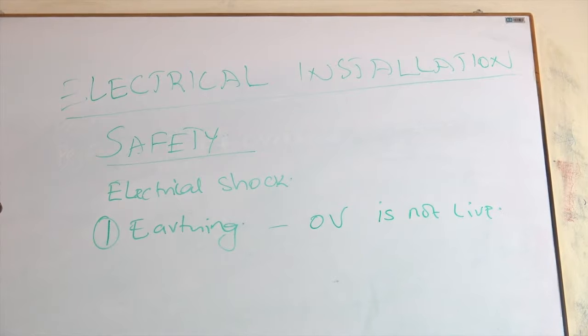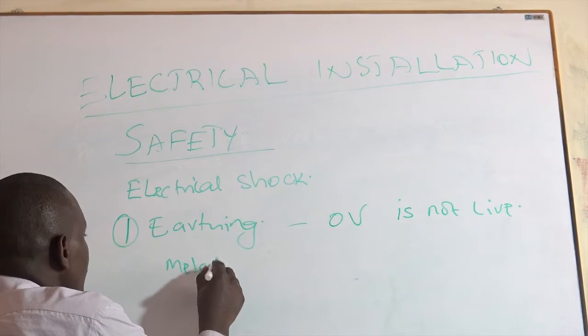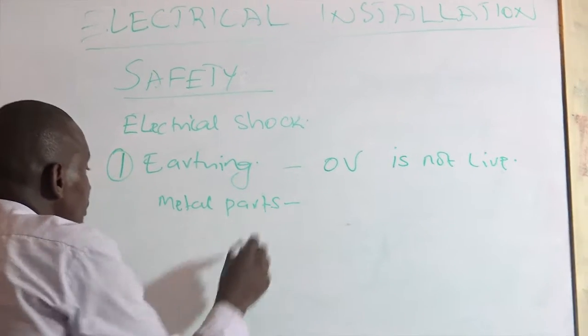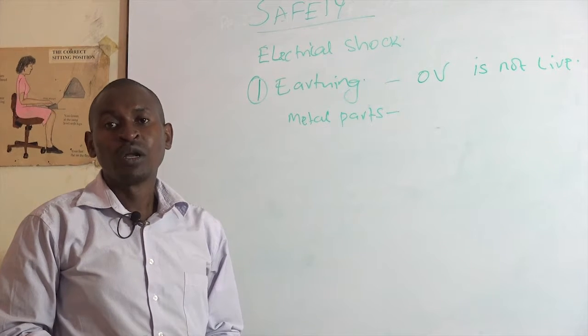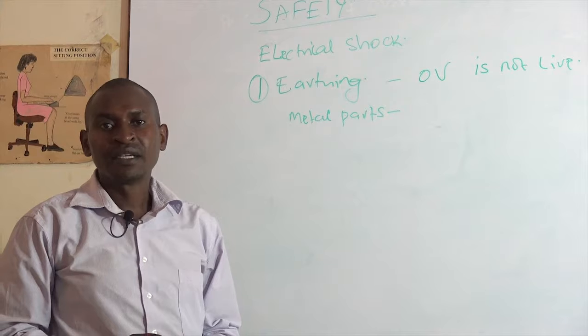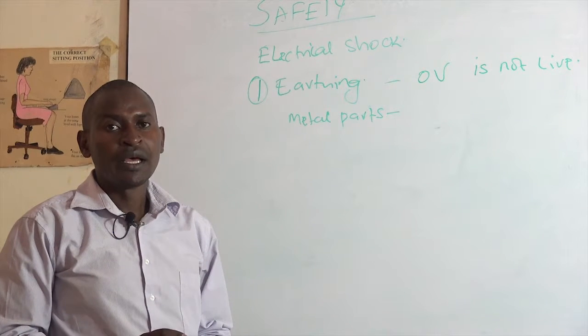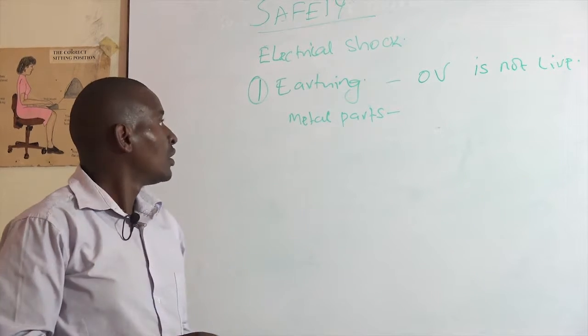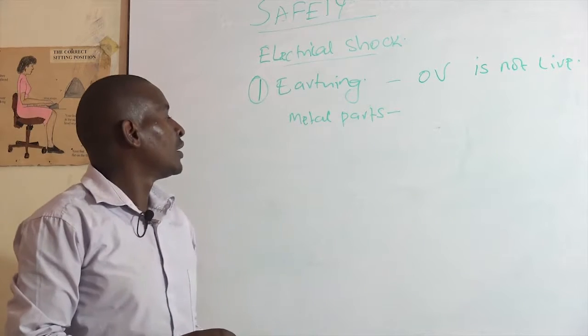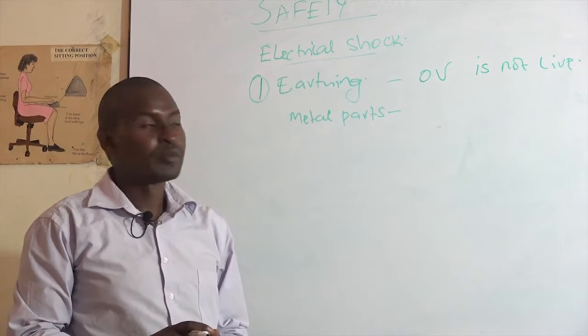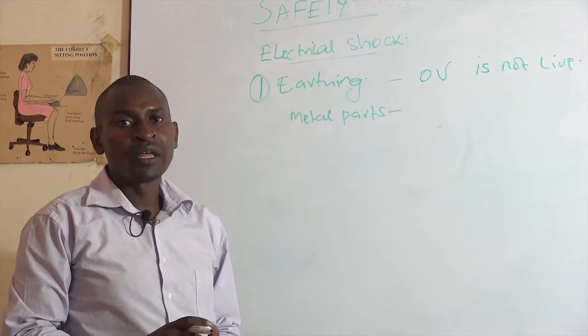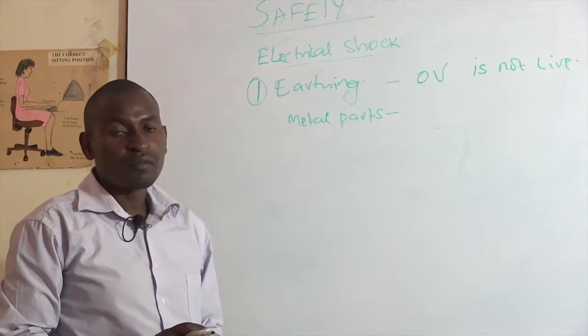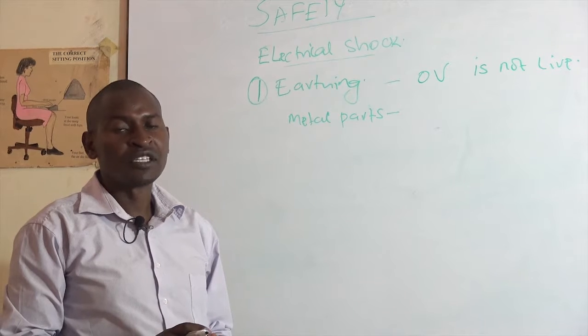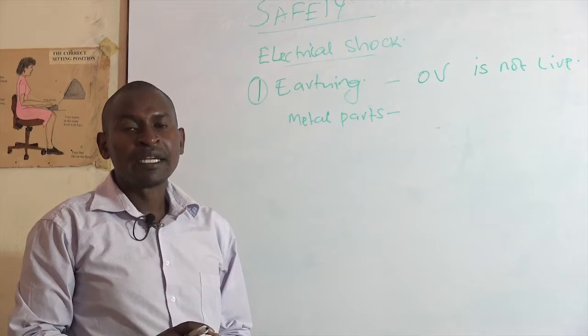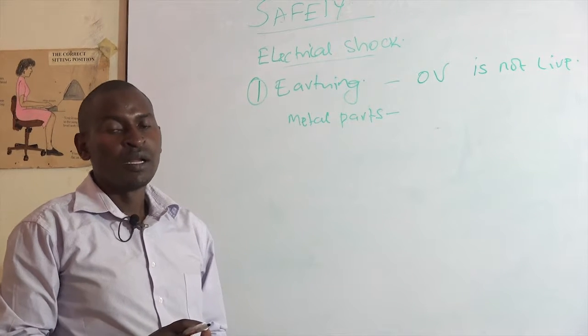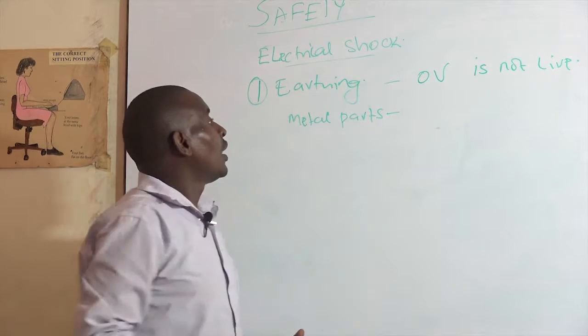This is because all metal parts can be electrically charged, and when they are electrically charged, they assume a potential, and if you come into contact with those metal parts, then you are going to get an electric shock, and that might not be a very pleasant experience. So by earthing, we make sure that all exposed metal parts forming part of the installation, be it the equipment or any metallic part or metallic framework, are at zero potential. And how do we do this?